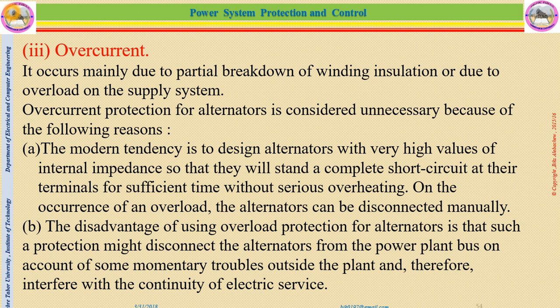The third fault of a generator is overcurrent. It occurs mainly due to partial breakdown of winding insulation or due to overloading of the supply system. That means when the winding insulation becomes weak, there will be contact at that time and there will be overcurrent. Overcurrent protection for the alternator is considered unnecessary because of the following two reasons.